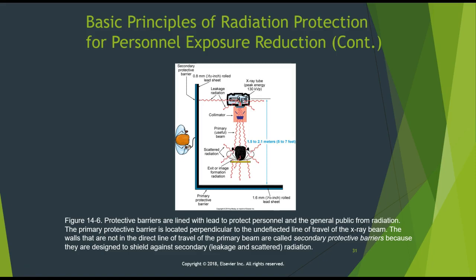And this is a good picture. Okay, this is our X-ray tube. This is our primary beam. This is our wall bucky. And this is your primary barrier, because this is the wall that's perpendicular to that primary beam right here. It has to be thick enough to attenuate any of those primary photons coming through that wall to keep personnel or non-occupational personnel safe on the other side of this wall. So the minimum for a 130 kVp beam is 1.6 millimeters of lead. The other walls that are not perpendicular to the primary beam are called secondary barriers, and we'll go over that as well.